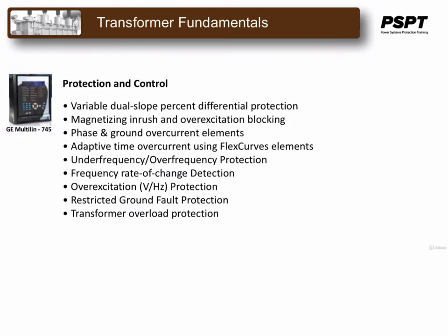For protection and control, the 745 has variable dual slope percentage differential protection, magnetizing inrush and overexcitation blocking, phase and ground overcurrent elements, adaptive time overcurrent using flex curve elements, underfrequency and overfrequency protection, frequency rate of change detection, overexcitation protection, restricted ground fault protection, and transformer overload protection.